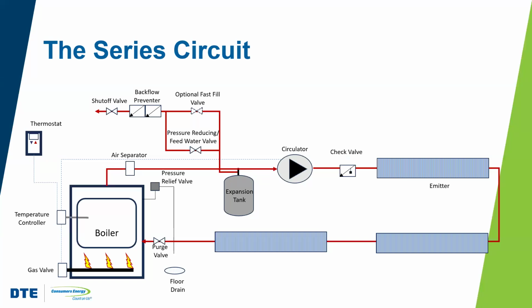That means that the individual emitters need to be sized based on the temperature that they will encounter. Very often installers will average the water temperature and size the emitters based on that. That can lead to oversizing at the first emitter and potentially undersizing at the last emitter, which means that spaces in the house will be under or overheated, and then there will be spaces that won't necessarily be comfortable, right?